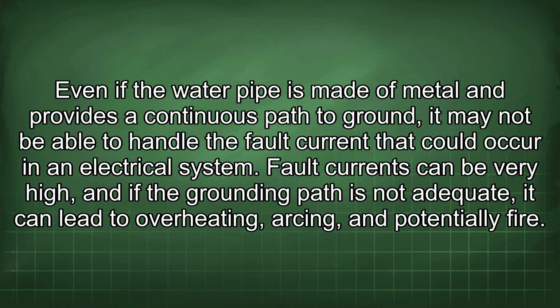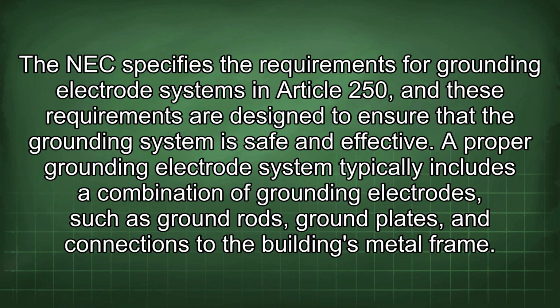Even if the water pipe is made of metal and provides a continuous path to ground, it may not be able to handle the fault current that could occur in an electrical system. Fault currents can be very high, and if the grounding path is not adequate, it can lead to overheating, arcing, and potentially fire. The NEC specifies the requirements for grounding electrode systems in Article 250, and these requirements are designed to ensure that the grounding system is safe and effective. A proper grounding electrode system typically includes a combination of grounding electrodes such as ground rods, ground plates, and connections to the building's metal frame.